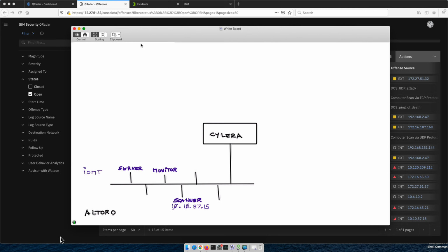And this is a particularly interesting technology because it not only detects incidents on the device, but it has a particular way of getting a clone of the different operating systems that these machines have. Some of them may be Win 7, Win 10, even Windows XP you find in some of those devices. So managing them, patching them, is something delicate. This technology clones an image of every one of those devices and scans it separately in order not to affect the performance of the device, and it collects a whole bunch of vulnerability information.